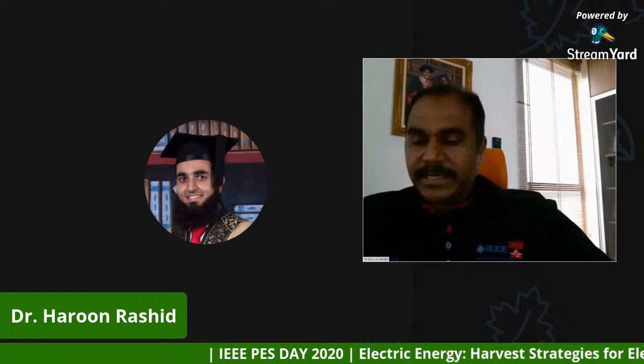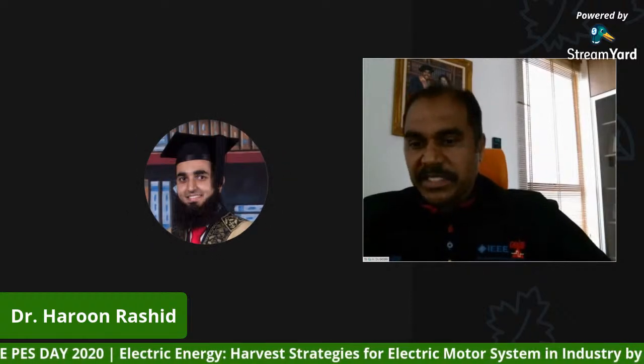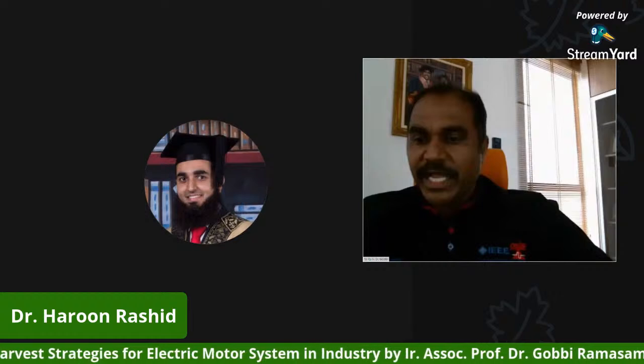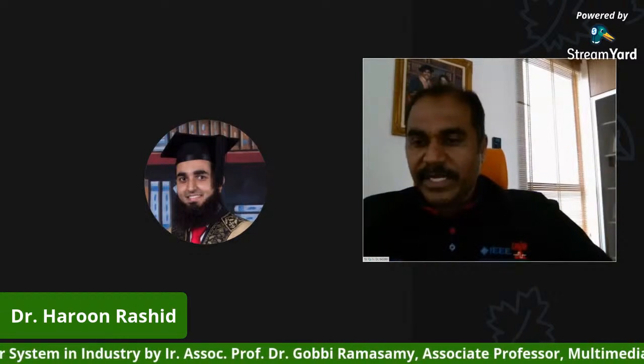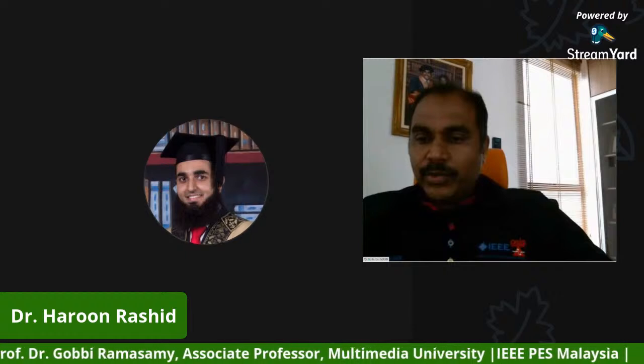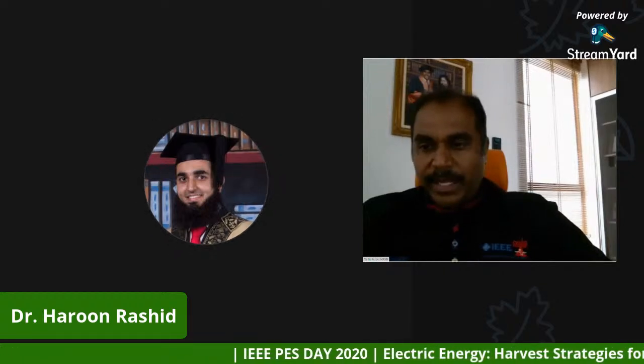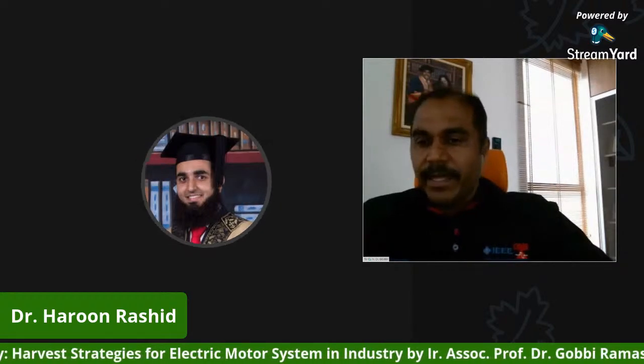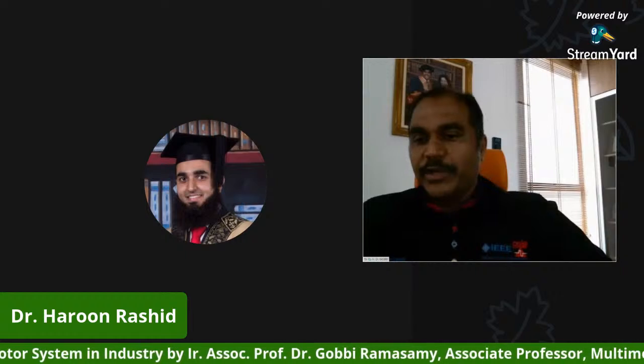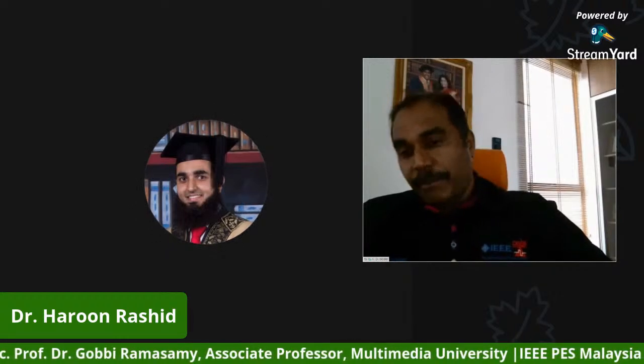Now, if the pump is oversized, but it is quite new, because it is only 5 years old, I don't think I will ask you to change the pump, because it's going to be costly. So yes, you can look into installing the VSD. You have to look at this, because this is for a chiller plant, so whether your pump can be run at low speed. We have done many projects, and yes, you can reduce the speed of the pump. When you reduce the speed of the pump, as I said, you will see huge savings in terms of power and energy.